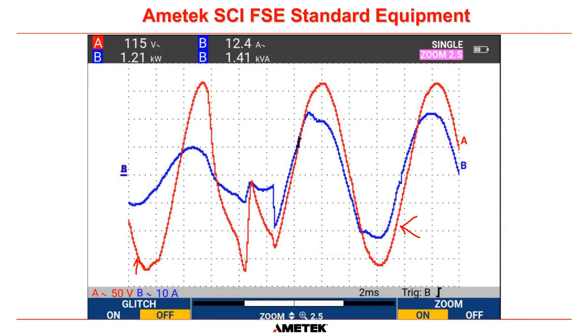And when I say crashed the inverter, what we did was we switched off the AC input to the inverter, so that it was running on batteries, and then we opened the battery input breaker, so the inverter had no DC voltage going to it, and the inverter just crashes. It's the worst thing that you can pretty much do to an inverter. So what you can see is at this point here, the voltage crashes, okay? But then the static switch picks up, and we are back to bypass voltage at this point here.